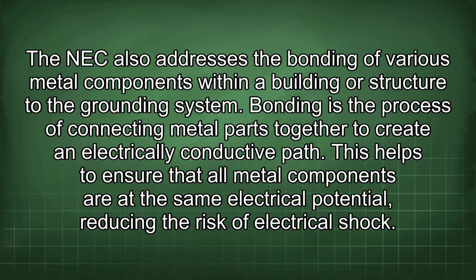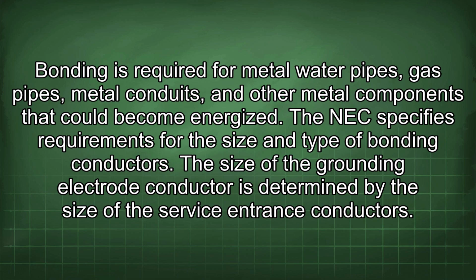The NEC also addresses the bonding of various metal components within a building or structure to the grounding system. Bonding is the process of connecting metal parts together to create an electrically conductive path. This helps to ensure that all metal components are at the same electrical potential, reducing the risk of electrical shock. Bonding is required for metal water pipes, gas pipes, metal conduits, and other metal components that could become energized. The NEC specifies requirements for the size and type of bonding conductors.